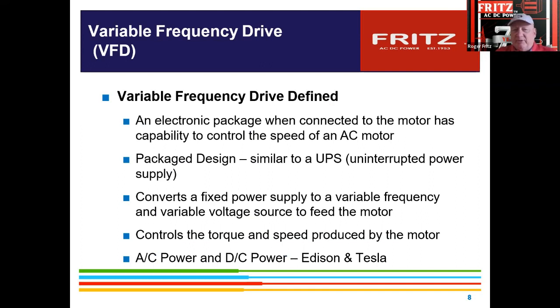So variable frequency drive defined, basically, is an electronic package that, when connected to a motor, is capable of controlling the speed and power to that motor. They're a package design. Some people don't realize an uninterruptible power supply is basically a hybrid VFD. It's just fixed frequency output, but they're able to regulate and make sure that power is steady. And then they sometimes use DC batteries on the DC bus circuit to regulate. So even if the power is fluctuating out there, it always has the DC to still build the output correctly. And it basically controls the torque and the speed of the motor.